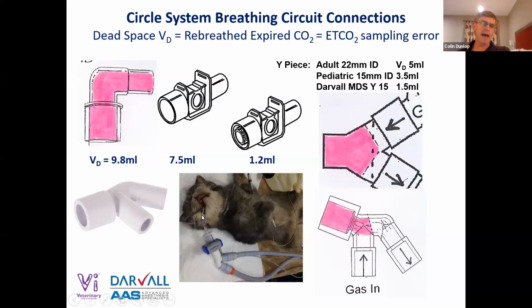So if I just had the cat, that adapter connected to the Y piece, if it was a standard adult Y piece, the volume of the gas we have to rebreathe is this bit down here in the Y piece. The adult Y piece, a 22 millimeter one, would be about 5 to 7 mils. In a pediatric 15 millimeter Y piece, it'd be about 3.5 mils. And we make a new Y piece that you can see in this picture here, funny looking shape thing, and it only has about 1.5 mils of dead space.